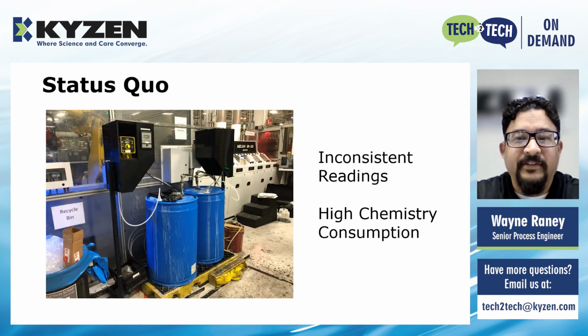We had previously installed two CCSs, one on the wash and one on the rinse tank, but they are having problems of inconsistent readings and high chemistry consumption. Before our visit, we decided to do a couple of things while we were there, including a calibration check, changing the probes from a dip and tank style to an inline style, and adding a system idle function. We hope this helps the inconsistent readings and the high chemistry consumption.